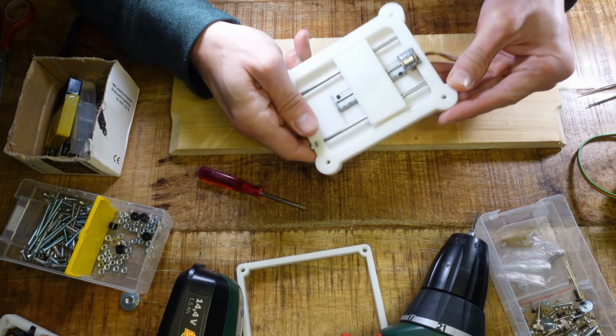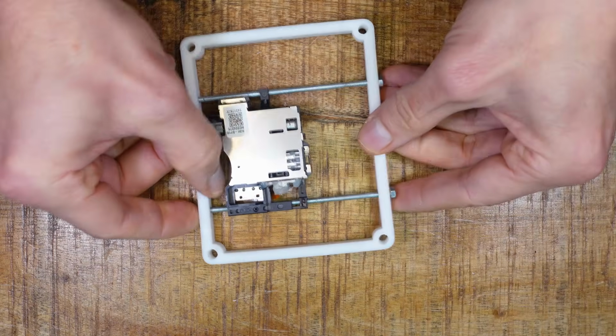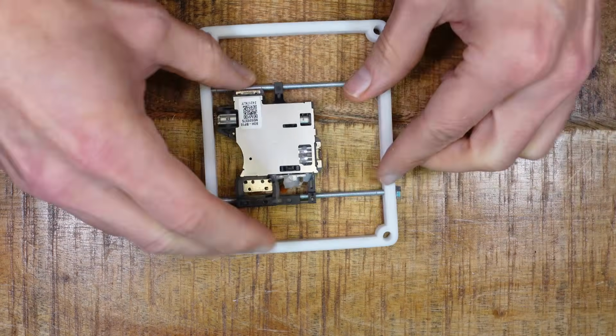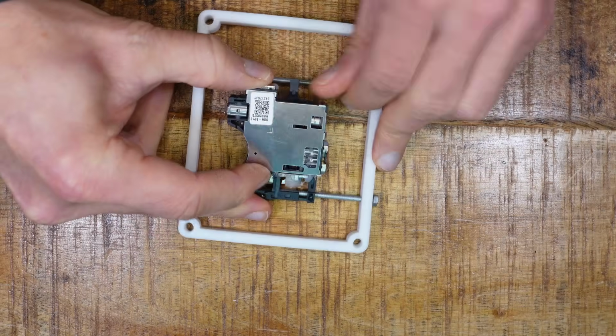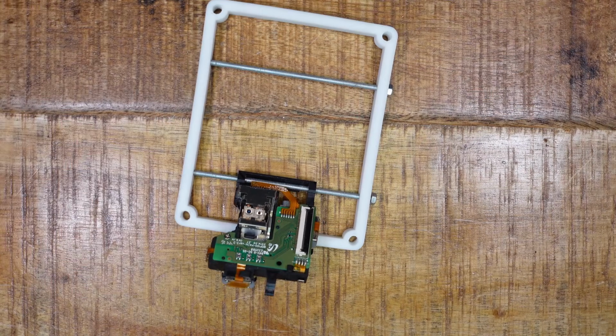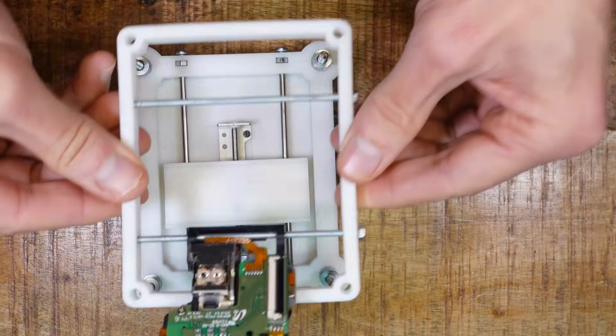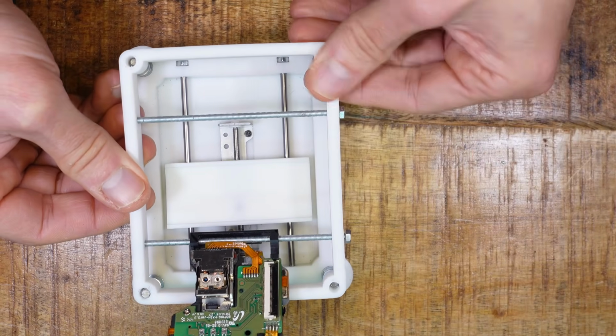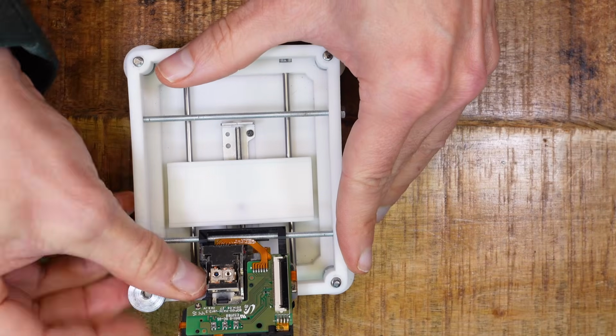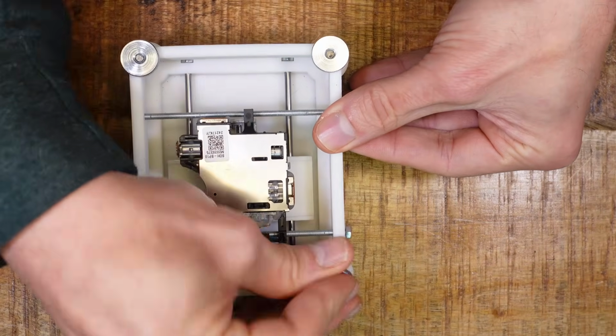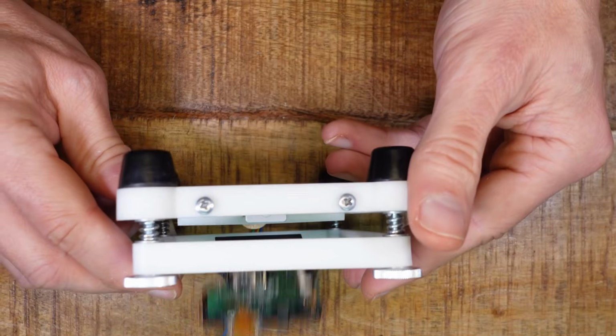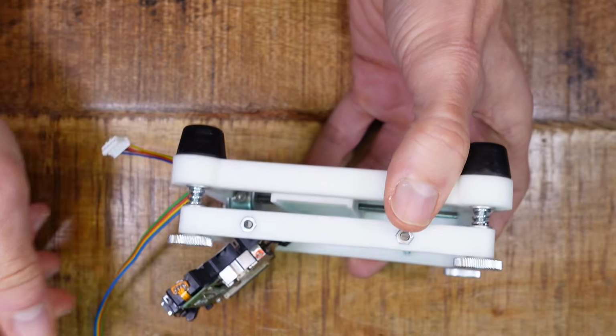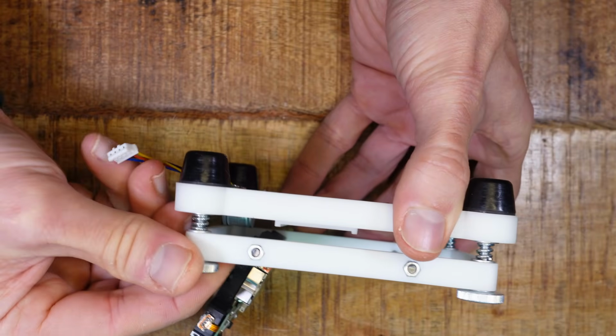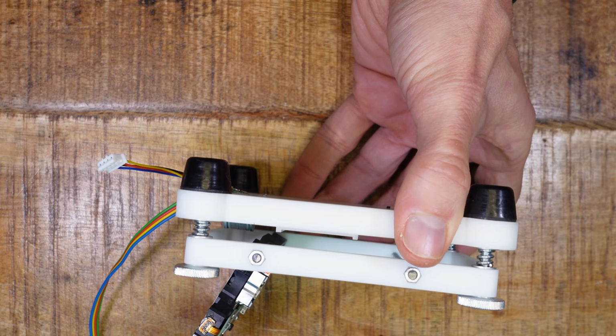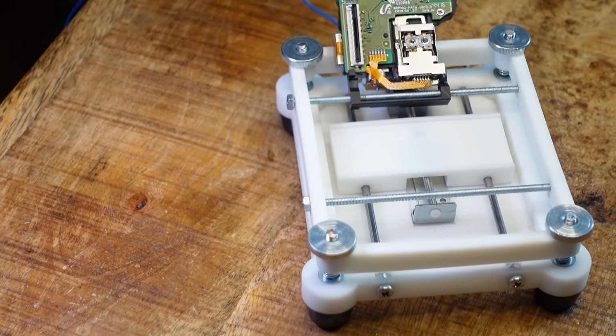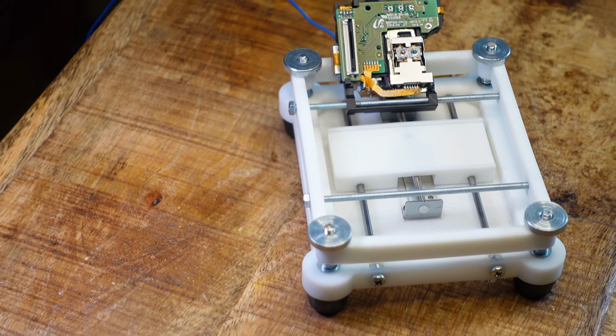There we go. The optical pickup unit gets loosely mounted between 2 threaded rods. This allows for shifting it from left to right to position it precisely above the specimen. It can be flipped open, making it easy to access the probe. Now I assemble this on top of the base with bolts, thumb screws and 4 springs in between. At the end, the springs and thumb screws hold it in place. This allows for a coarse adjustment of the distance between the pickup unit and the sample. That's all about the mechanics. A simple and straightforward construction, isn't it?